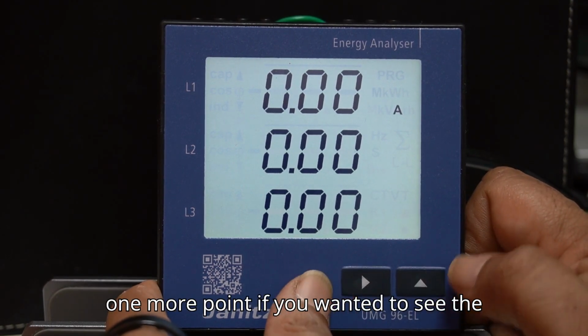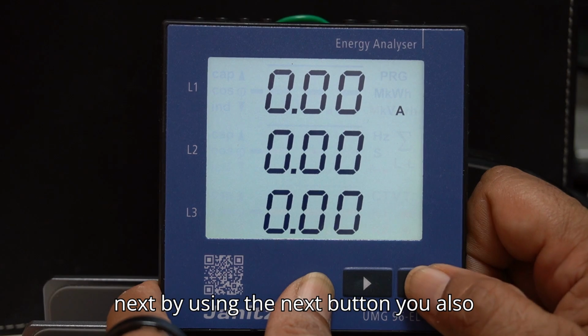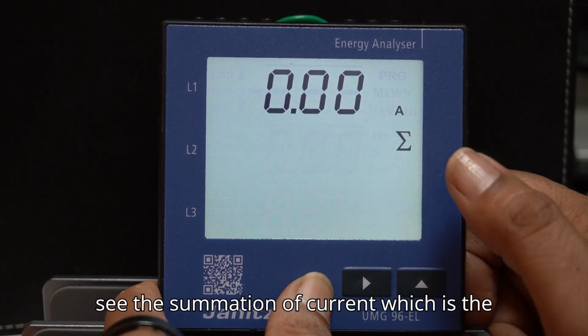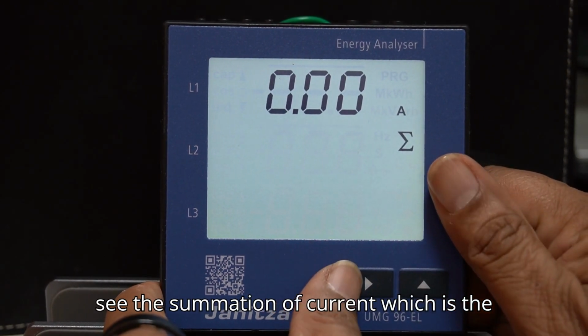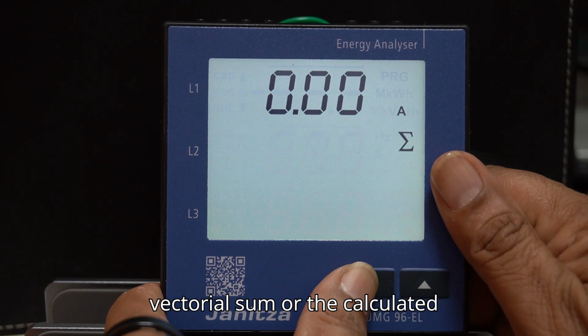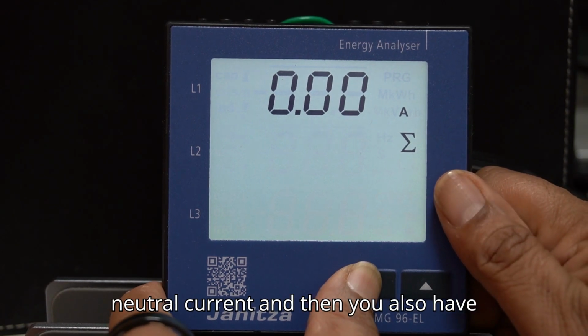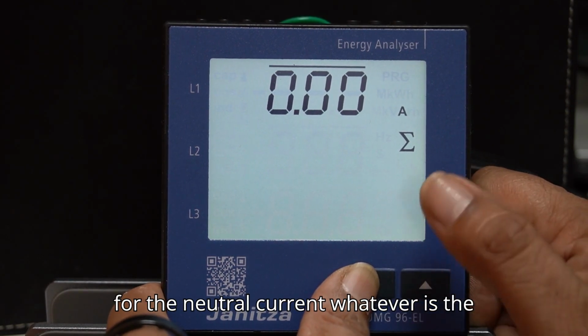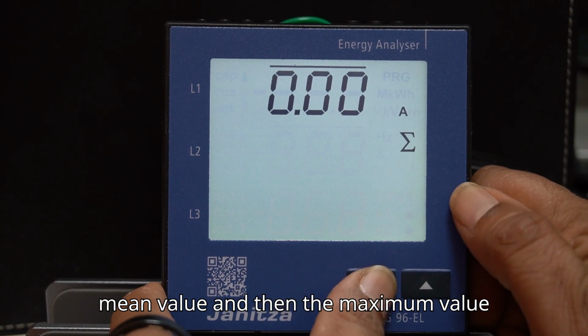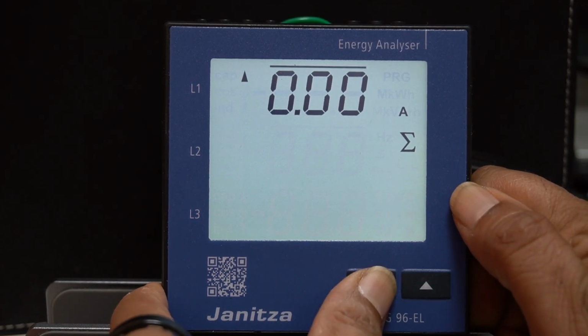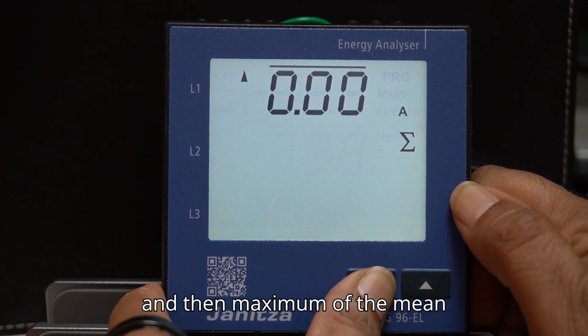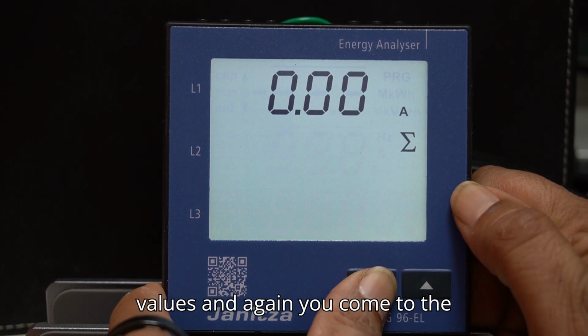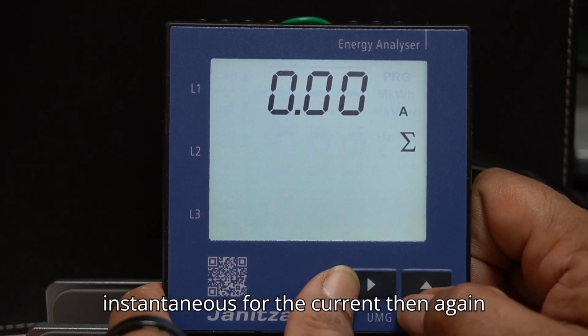If you press the next button, you also see the summation of current, which is the vectorial sum or the calculated neutral current. And then for the neutral current you have the mean value, and then the maximum value, and then the maximum of the mean values, and again you come to the instantaneous current.